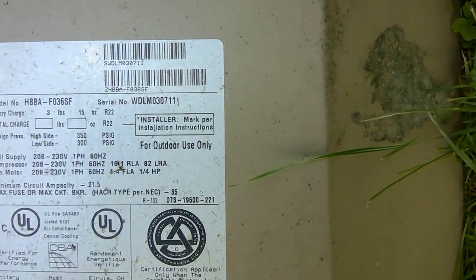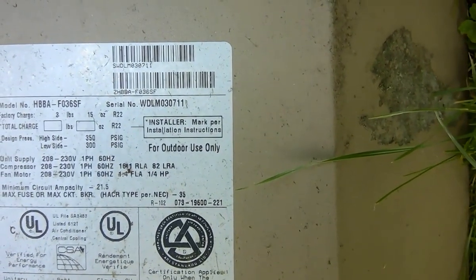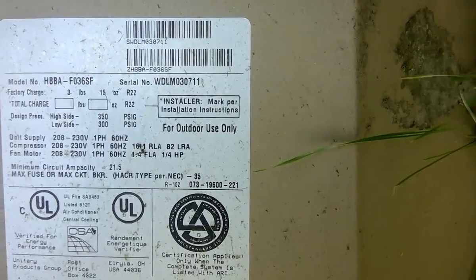So you can see that the spec on the sheet is 82 lock rotor amps and 16.1 running amps. So I was a little under before. Like I said, I think it was 77. We'll have to go back to the video and look. And now I'm at 53. So that's it for now.